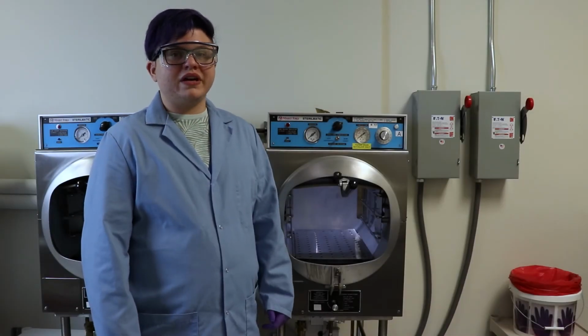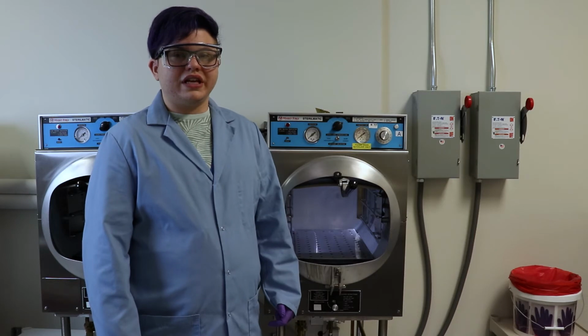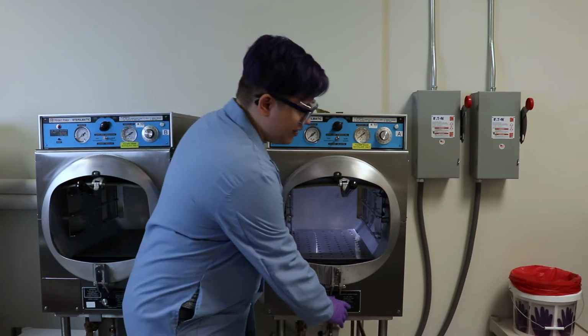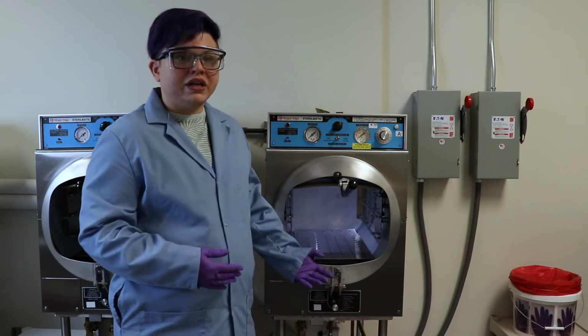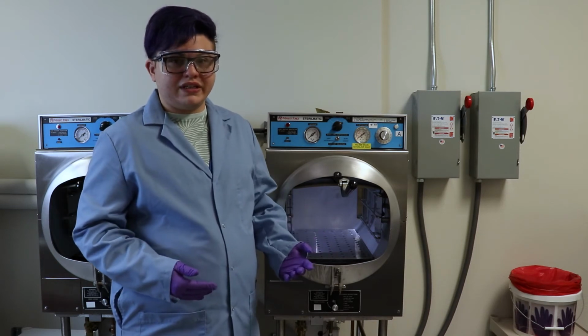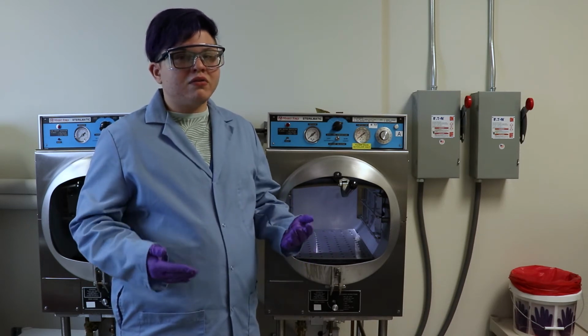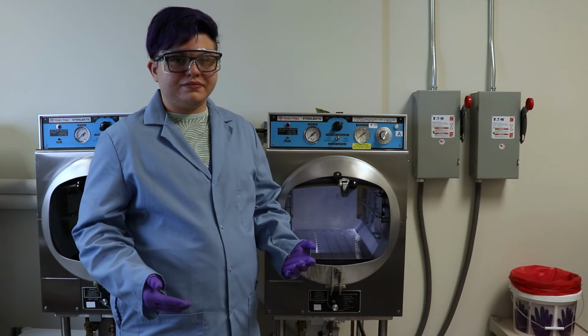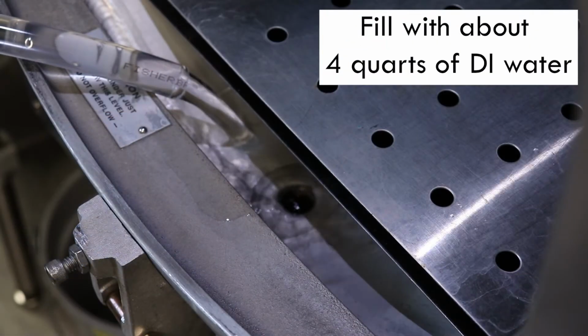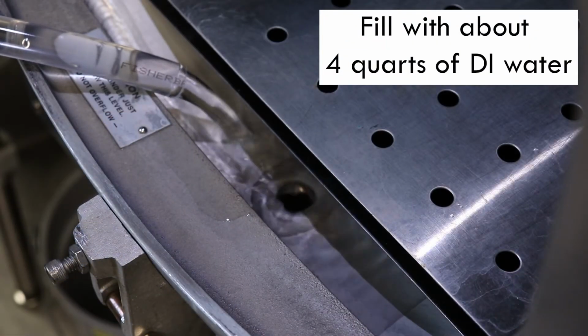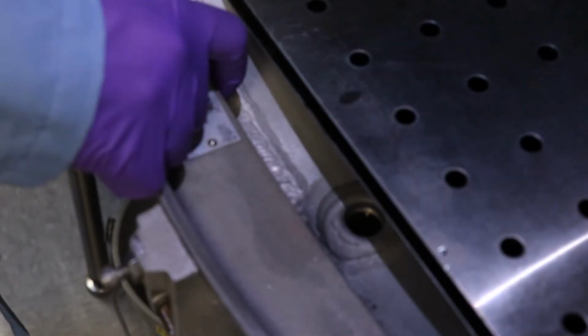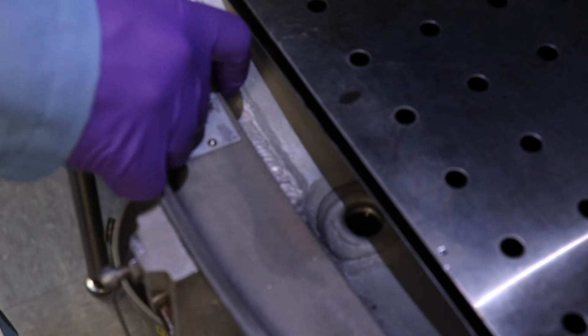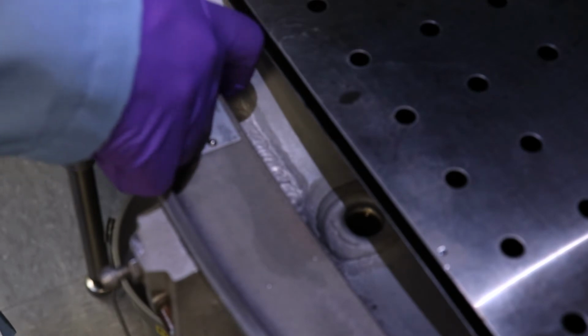Next, we'll be going over how to load the autoclave. First, you want to shut the drain valve and then load it with DI water specifically. You use about 4 quarts of water per load. Four quarts is about 1 centimeter or 1 finger width below the lip of the door.